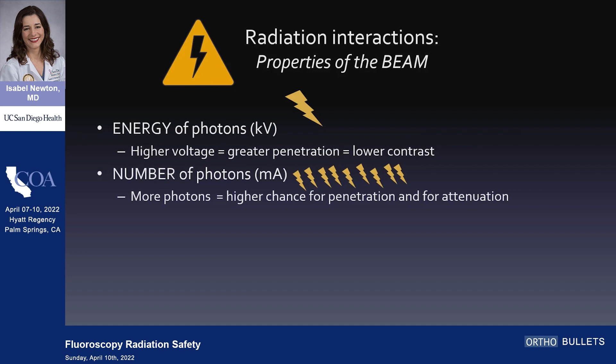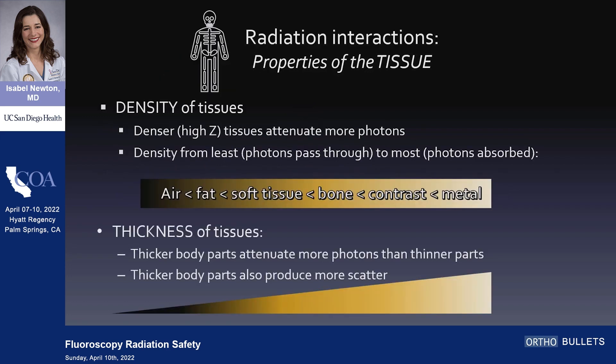When we talk about properties of the beam, it's important to understand two concepts. One is the energy of the photons, described as the KV. Higher voltage means greater penetration, so all the photons are going to get there and you'll have lower contrast — if all photons get there, you've got no image. So you want the differential arrival of these photons. Then there's the number of photons, that's the MA. More photons means a higher chance for some to reach the detector, but also a higher chance of attenuation.